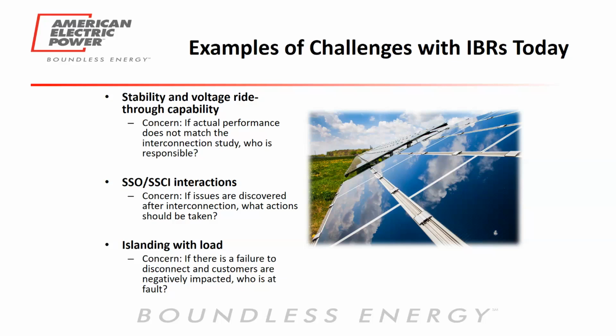The second issue here is again a very technical one, but certain types of wind farms can have subsynchronous oscillation, SSO, and subsynchronous control interaction, SSCI. Basically these very complex machines, the wind farm, and the series compensation placed on the lines can interact, which can be bad for the plant in terms of actually damaging equipment, but also can cause issues with the operation of the transmission grid and that equipment as well.